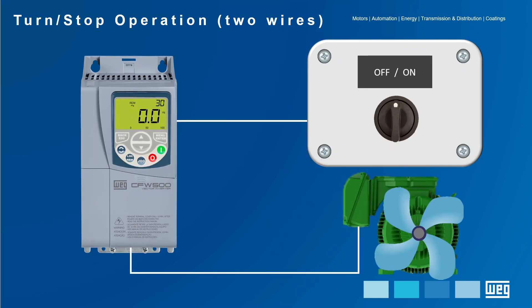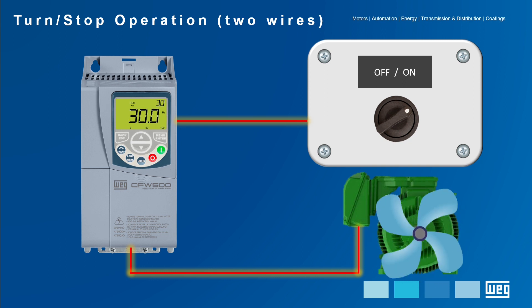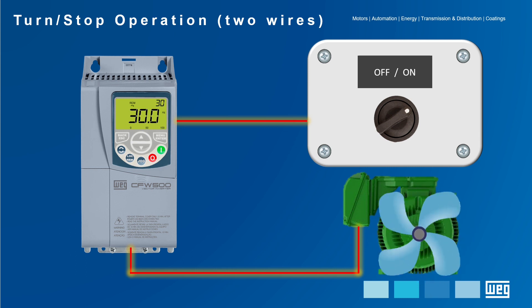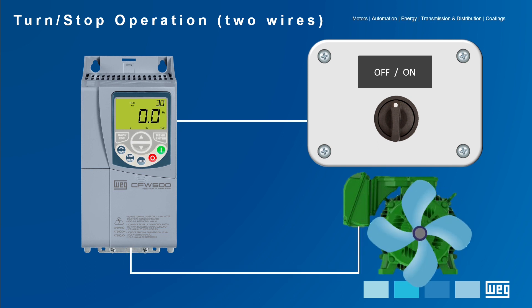Once the physical connections are completed and the parameters are set, here is an operation representation for the two-wire TURN STOP command. When switching the knob to the ON position, it closes its normally open contact and the drive will accelerate the motor up to the speed reference set by the HMI — in this example, 30 Hz. Switching to the OFF position, the NO contact opens and the drive will turn off the motor respecting the deceleration ramp.